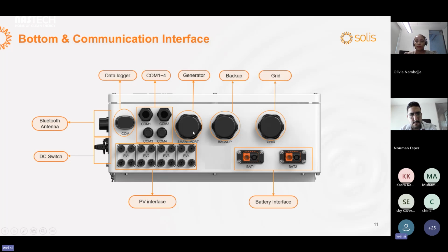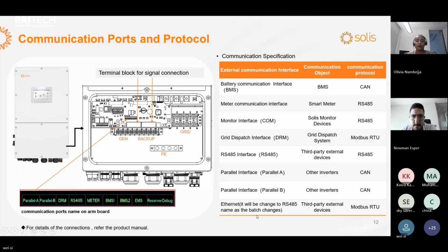And a smart port, which we also call the generator port, is used for the generator connection, but it can also output power to supply some loads. But the priority is very low, lower than the backup port. The backup port is used to connect the critical load, and this is the grid port connecting to the AC grid. We have two battery ports to support two battery connections. If you open the wiring box cover, you can see these ports on the board.